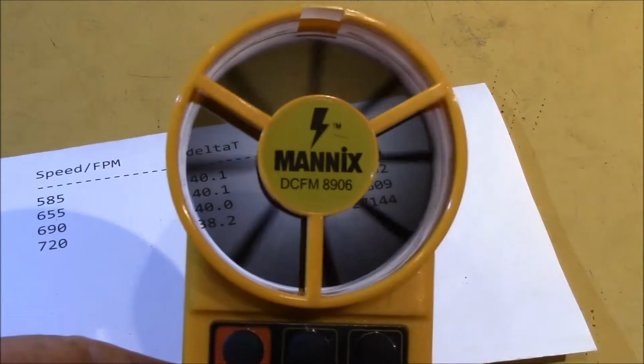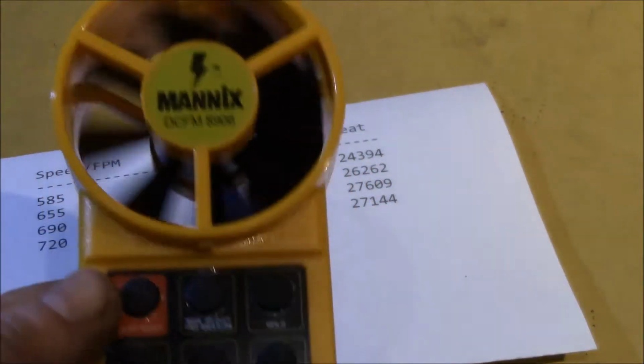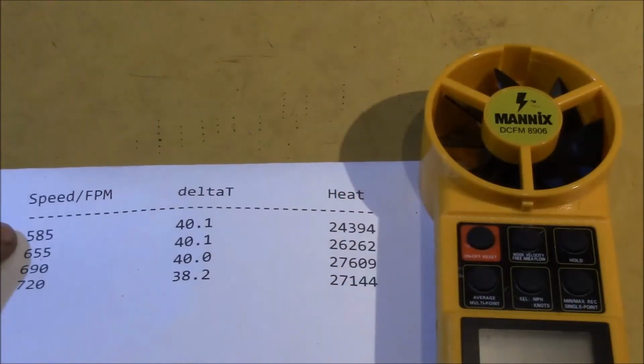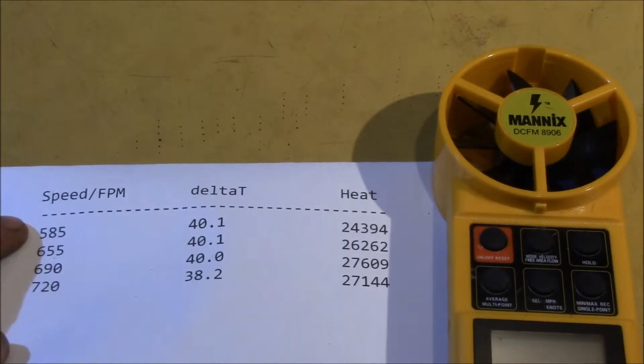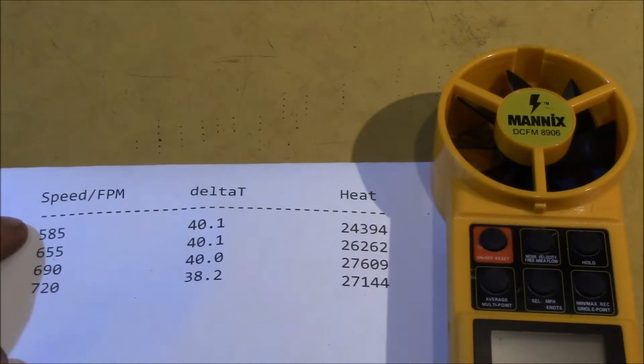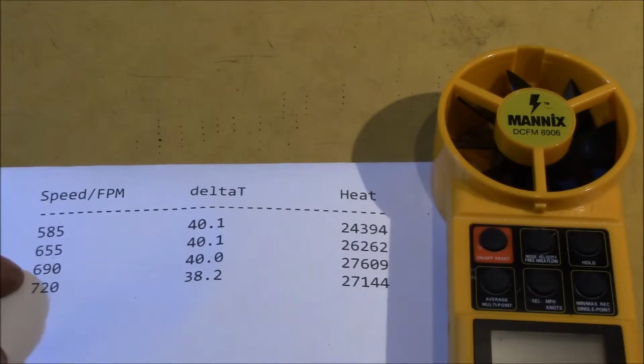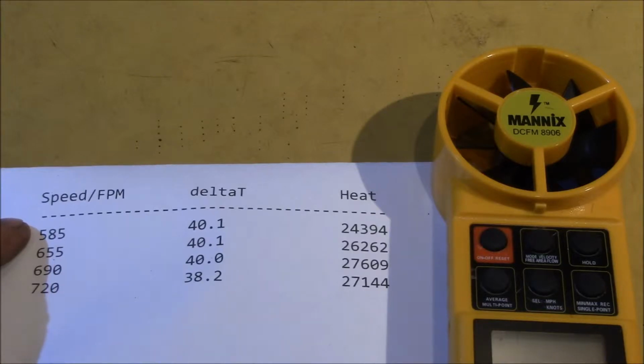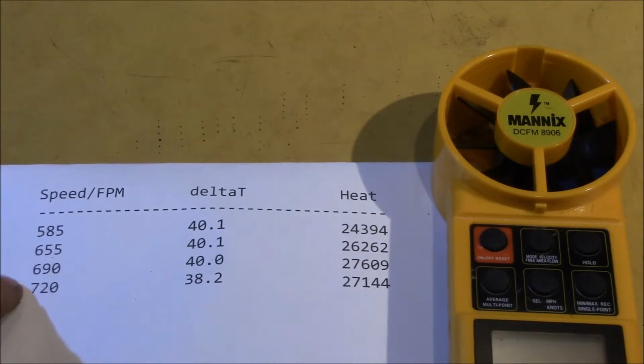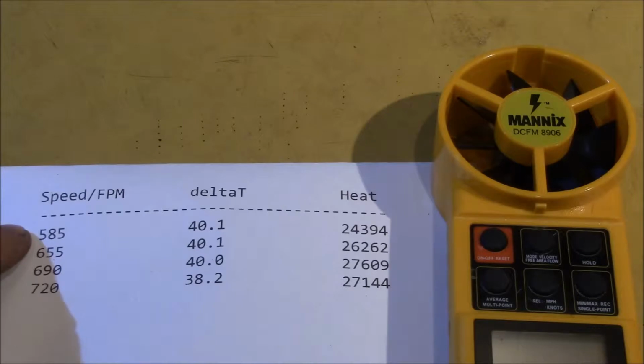It has a little anemometer, and there's a temperature probe someplace in the airstream. I recorded feet per minute, since that's the unit it comes up in, but you could change it to meters per second, miles per hour, or knots, and if you calibrate it to your duct size, you can get CFM. But what matters is all of those are just calibration factors, they're constants.